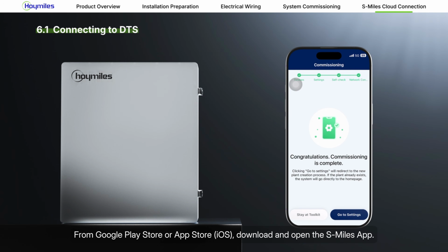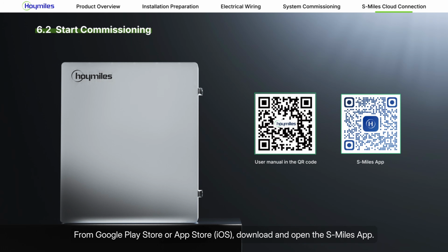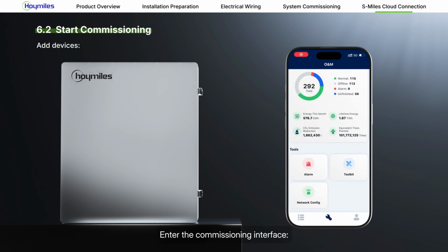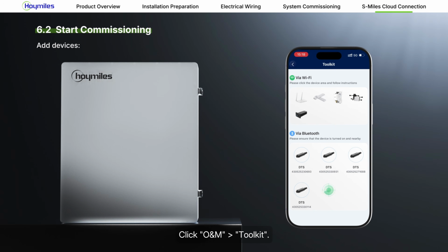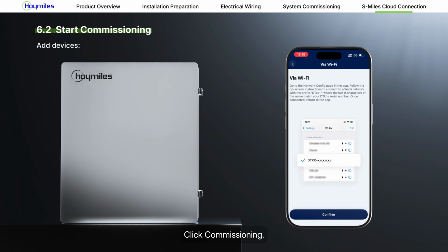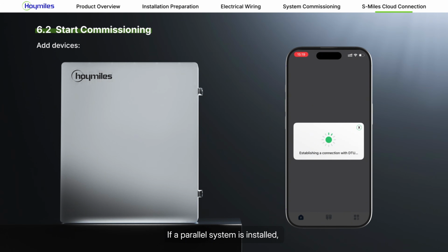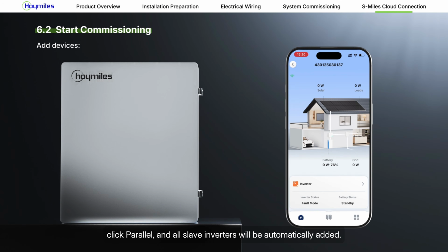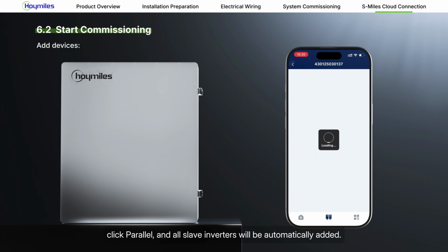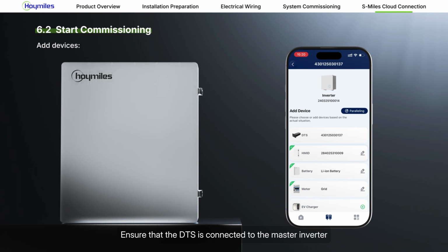From Google Play Store or App Store, download and open the S-Miles App. Enter the commissioning interface. Click O&M Toolkit. Click Commissioning. If a parallel system is installed, click Parallel, and all slave inverters will be automatically added. Ensure that the DTS is connected to the master inverter, and the secondary inverters are connected to the master inverter via communication cables to communicate with the DTS. One DTS can communicate with up to 10 inverters.